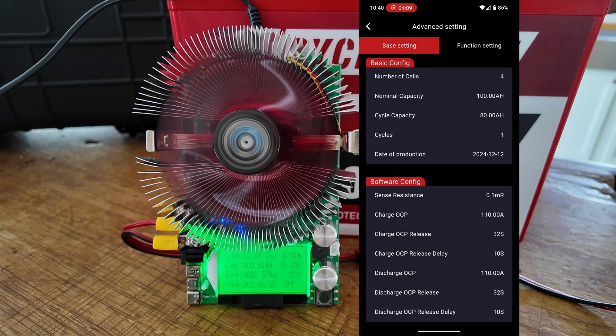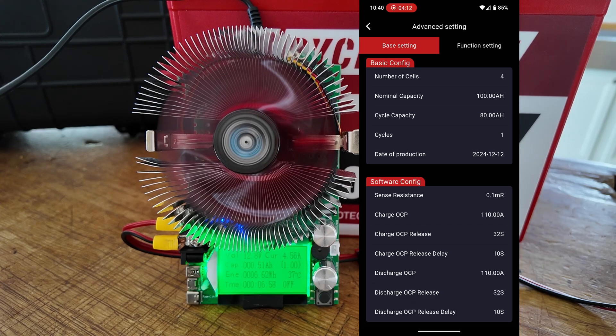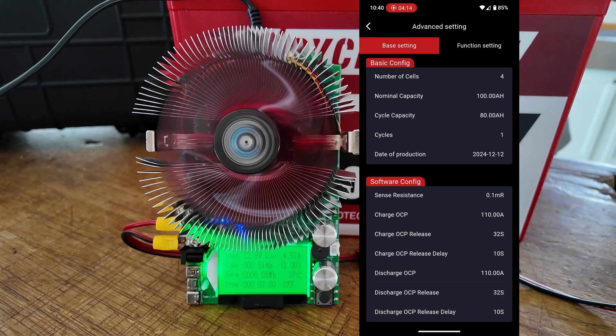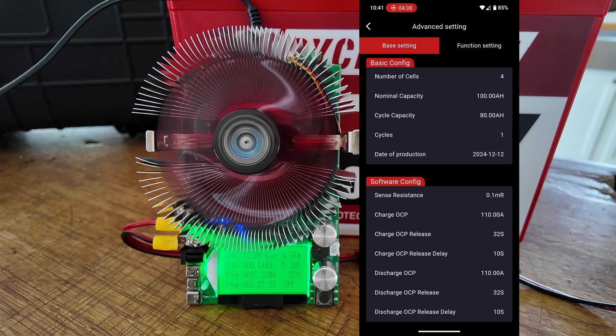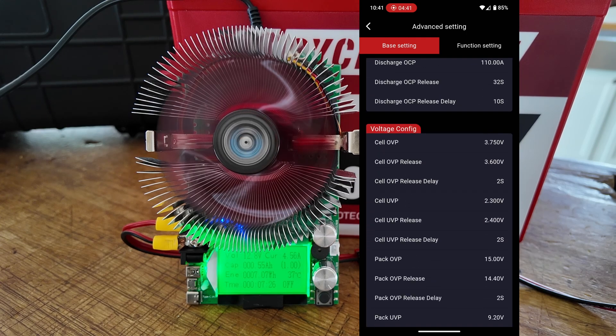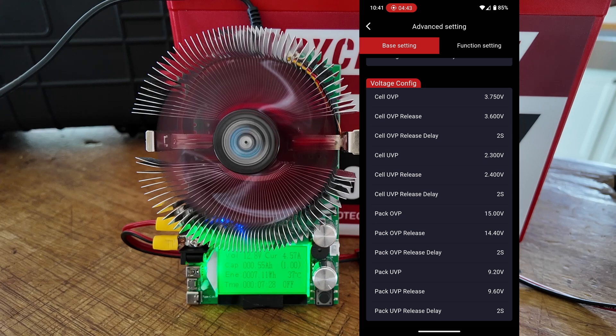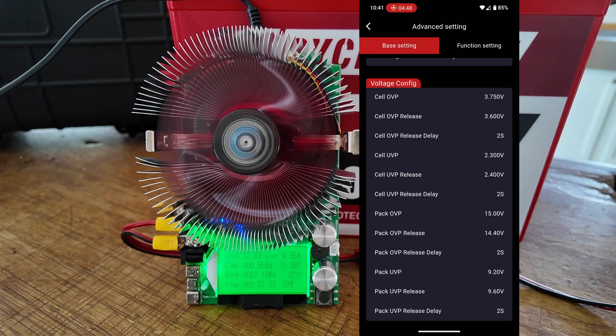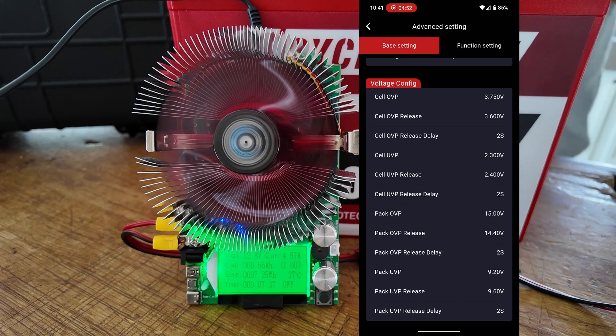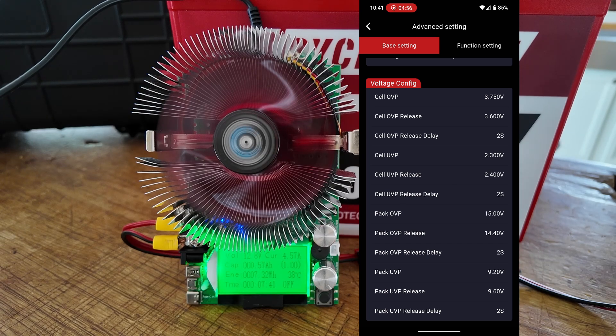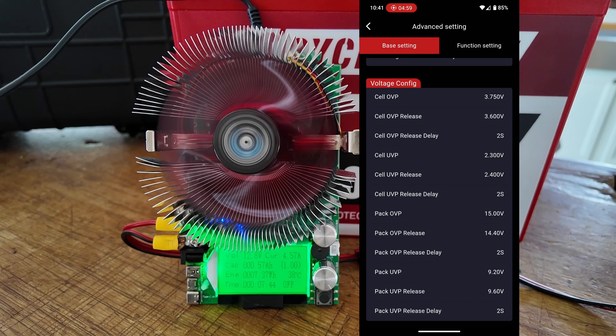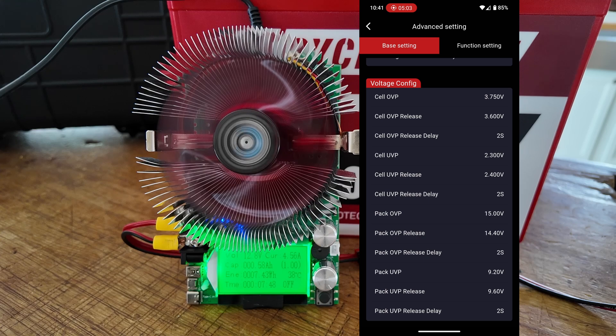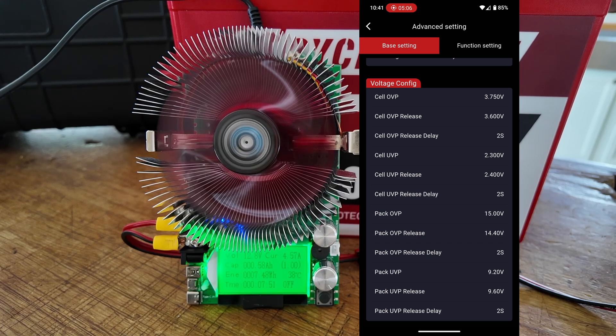And now you are able to completely reprogram this BMS. It's got all of the different settings, and you can set this up exactly the way you want it. I'm going to skip past the basic configuration and the software configuration. I want to come down here to the voltage configuration and take a look at this. We can do over-voltage protection for the individual cells, and then we can do an over-voltage protection release. In other words, if it gets over 3.75 volts for an individual cell, it's going to shut down charging.